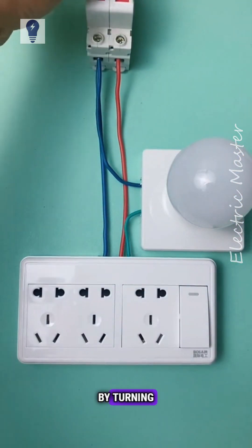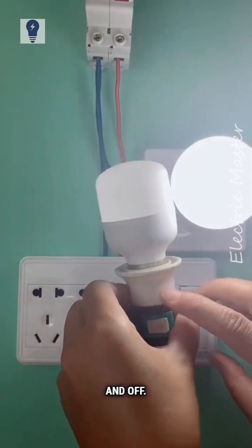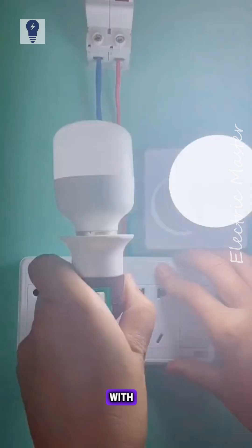Once installed, we'll test it by turning on the power. Test the light on and off. The socket should always have power. This is how to wire a 15-hole socket with a single switch.